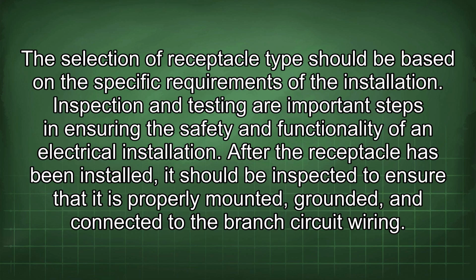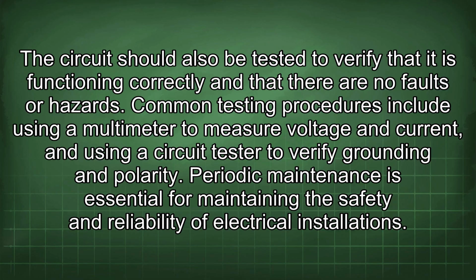Inspection and testing are important steps in ensuring the safety and functionality of an electrical installation. After the receptacle has been installed, it should be inspected to ensure that it is properly mounted, grounded, and connected to the branch circuit wiring. The circuit should also be tested to verify that it is functioning correctly and that there are no faults or hazards.